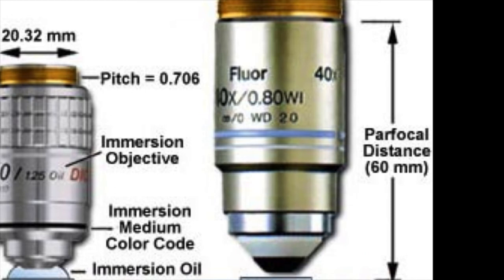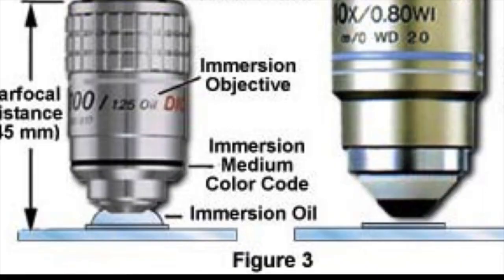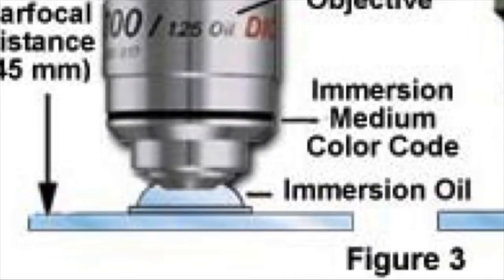Another important feature is that these are now infinity-corrected objectives, whereas before they were 160-millimeter tube length. Another important feature for you to see is the immersion. Here is an immersion objective where we have a drop of immersion oil between the objective and the cover slip that's on your slide, which contains your specimen. You might be using immersion oil, water immersion objective, or glycerol immersion objective. All three are available on the Leica confocal microscope.